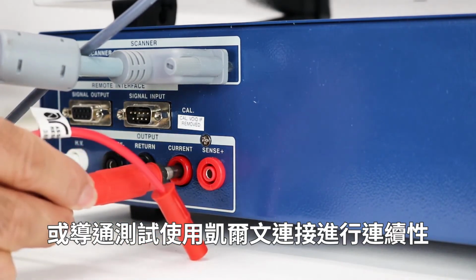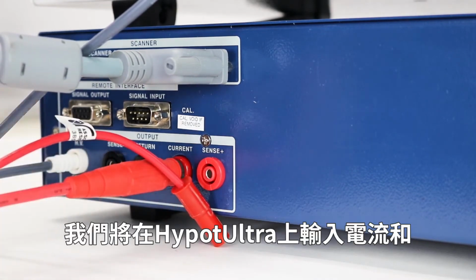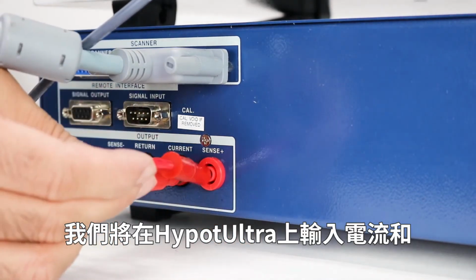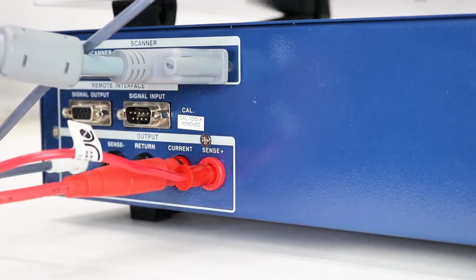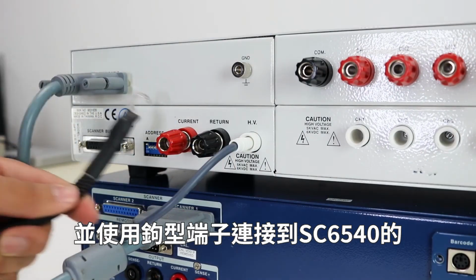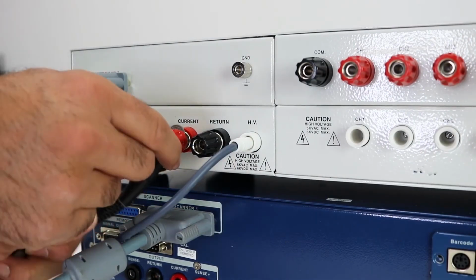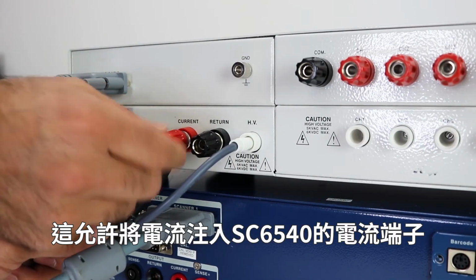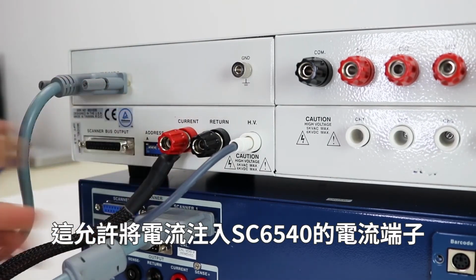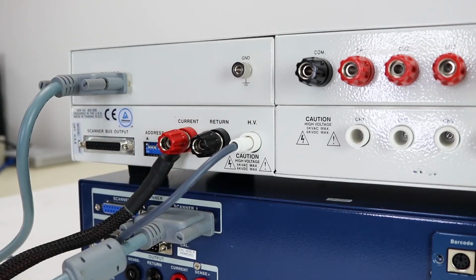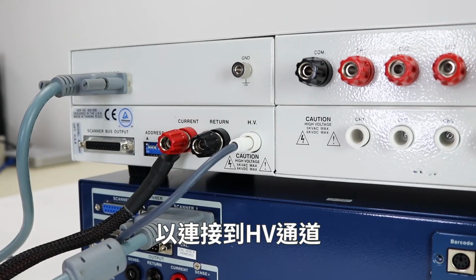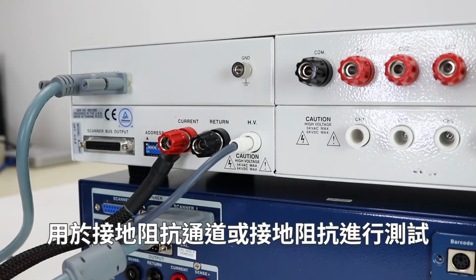Using the LEMO and sheath Kelvin connection, we're going to input the current and the Sense Plus on a HypotULTRA and use the hook lug to connect on the current terminal of the SC6540. This allows for an injection of current into the current terminal on the SC6540 to either connect to the HV channels for continuity or ground bond channels for a ground bond test.